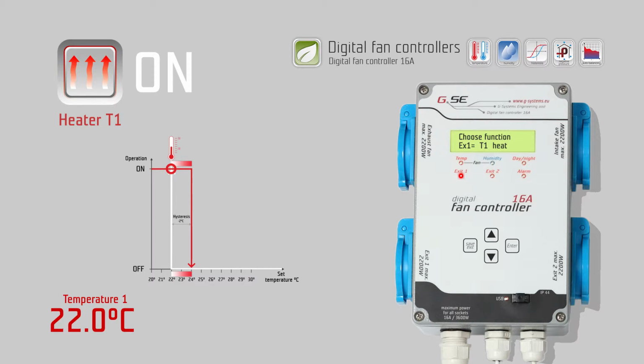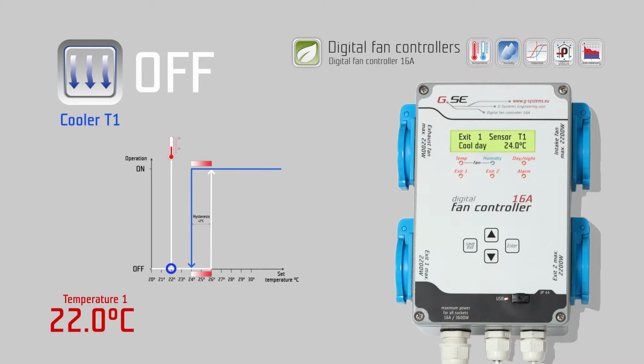Select the function Output Sensor 1 Cool, and press Enter. This function works the same way as Output Sensor 1 Heat, with the only difference that the hysteresis is reversed during the cooling. If the hysteresis is set to +2 degrees Celsius, and the day temperature is set to 24 degrees Celsius, then the cooler will switch on at 26 degrees, and switch off when it drops to 24 degrees. This contact will remain off until the value rises above 26 degrees Celsius.